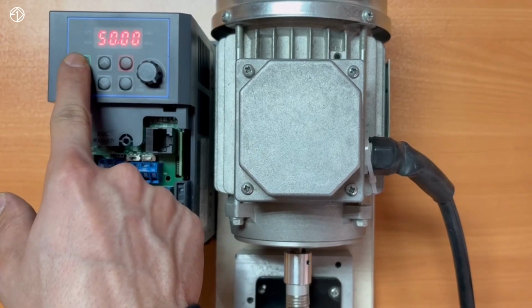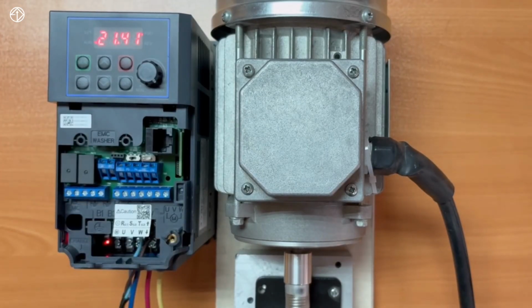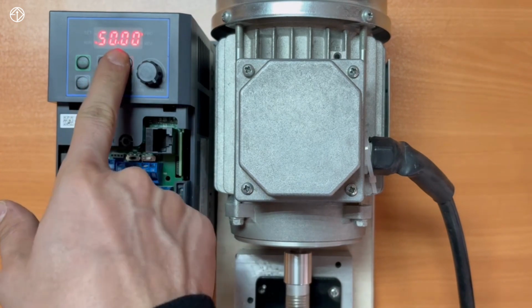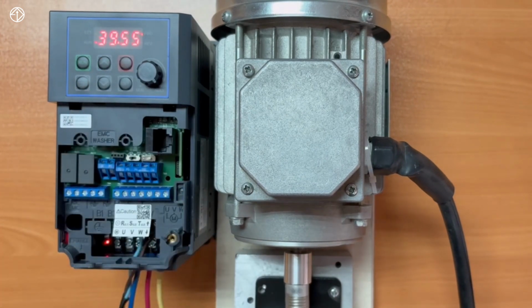Now I'll start my VFD. I wait for it to reach a frequency of 50. Now if I issue the stop command, it should take 10 seconds to go from a frequency of 50 to a frequency of 0. I'm going to stop it now. It takes the duration of 10 seconds, and in the end my electric motor stops. This was the stop using the deceleration time.